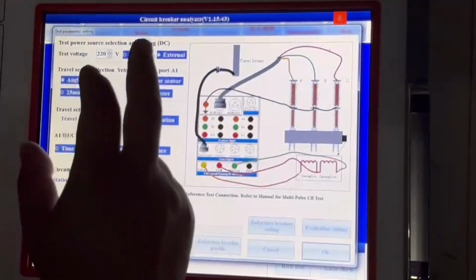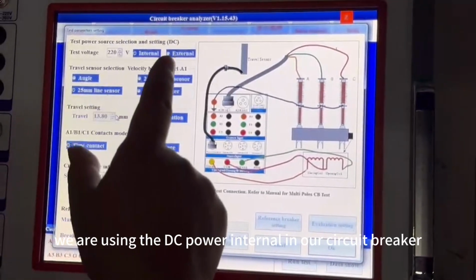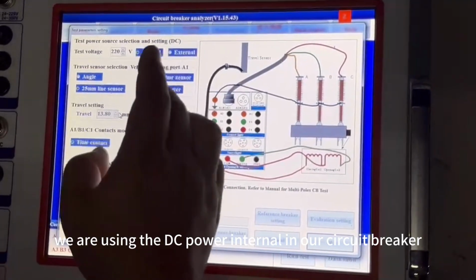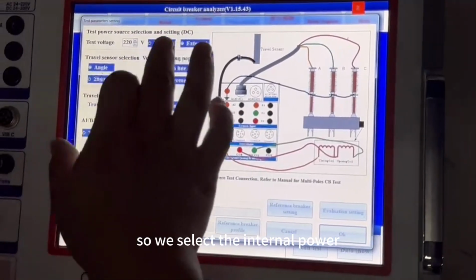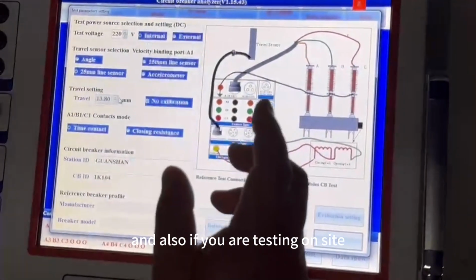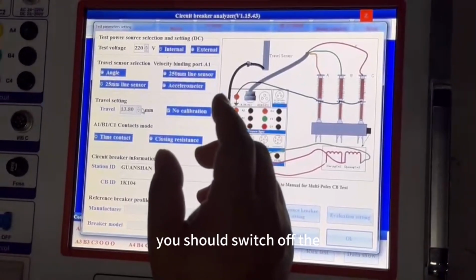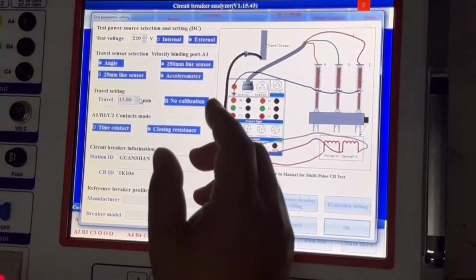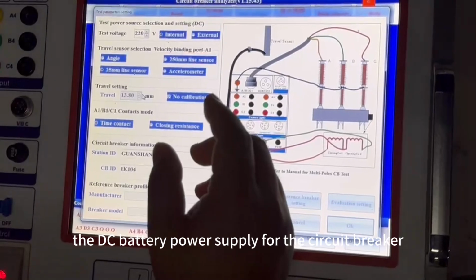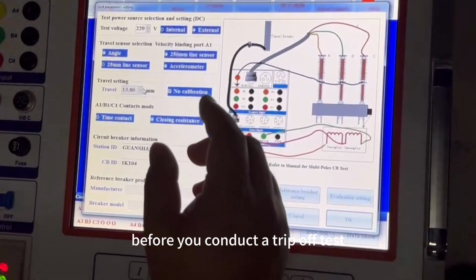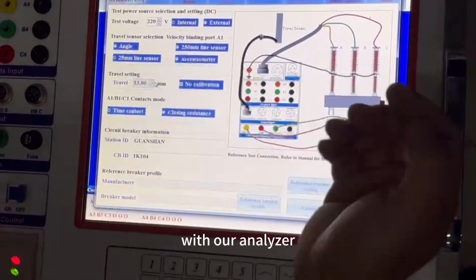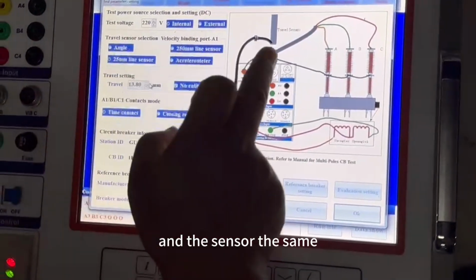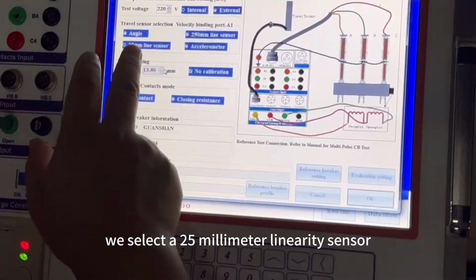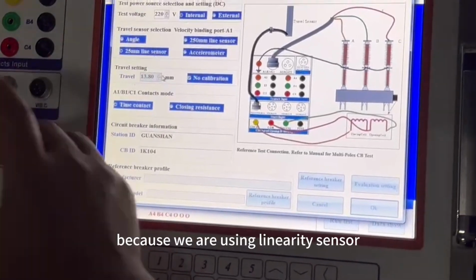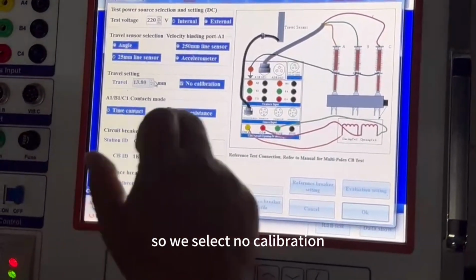And for the test setup window, now we are using the DC power internal to our circuit breaker, so we select the internal power. Also, if you are testing on site, you should switch off the DC battery power supply for the circuit breaker before you conduct the trip off test with our analyzer. And for the sensor, the same, we select the 25mm needle rod sensor. Because we are using a needle rod sensor, we select no calibration.